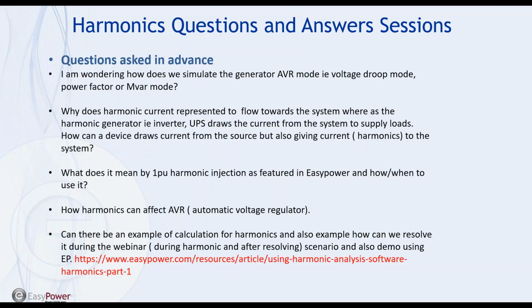Next question: why is harmonic current represented to flow towards the system, whereas a harmonic generator, such as an inverter or UPS, draws current from the system to supply loads? How can a device draw current from the source, but also give current back to the system? That's a good question, and on the surface, I guess it's hard to conceptualize. I have always modeled harmonic loads as harmonic current injection devices. I have a feeling this goes back to the Norton equivalent, where you have a 60 hertz voltage source, and then you're modeling the current injection at the other harmonics using a Norton type equivalent. That's the best I can answer this. It's a little bit into the theory of the modeling, and again, that's not my area of expertise.